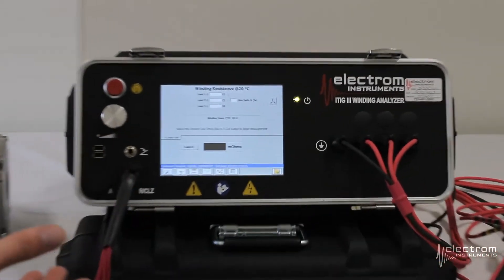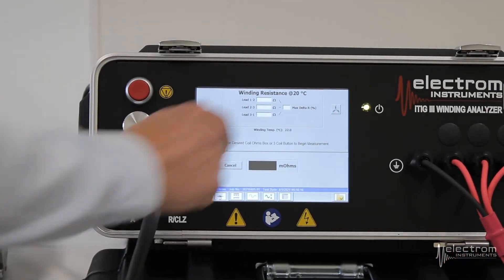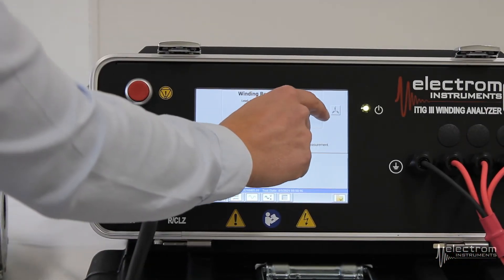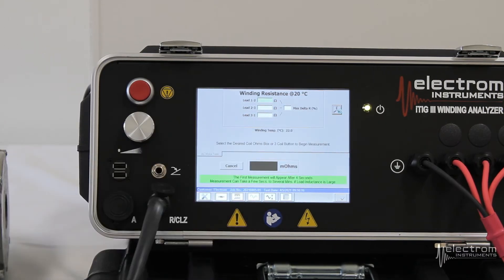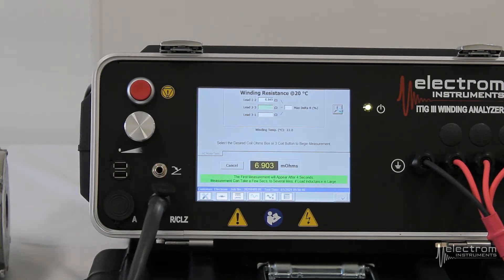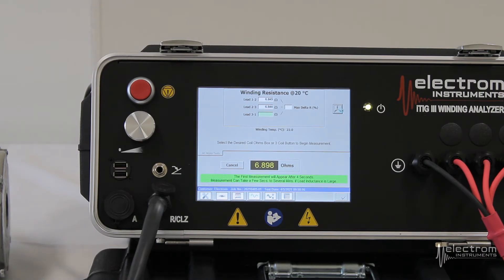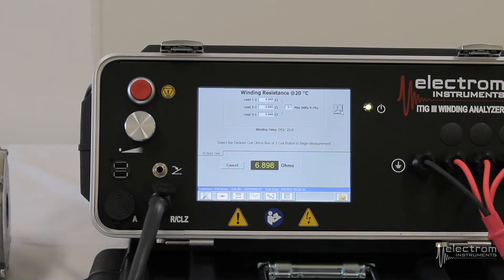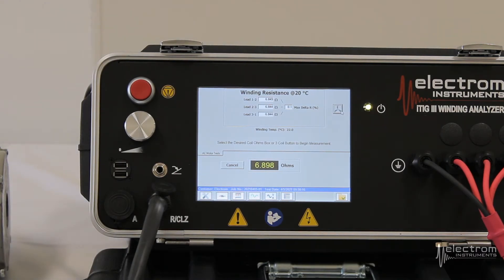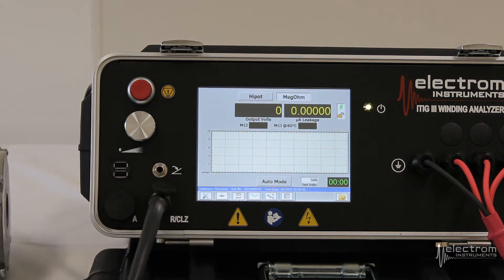Now we're ready to do the winding resistance measurement. We can simply click the star coil symbol. The tester will complete the measurement from lead one to two, two to three, three to one, and calculate our max delta R. In this case it turned out to be 0.1% — that's very good. We're now ready to move on to the megaohm measurement.